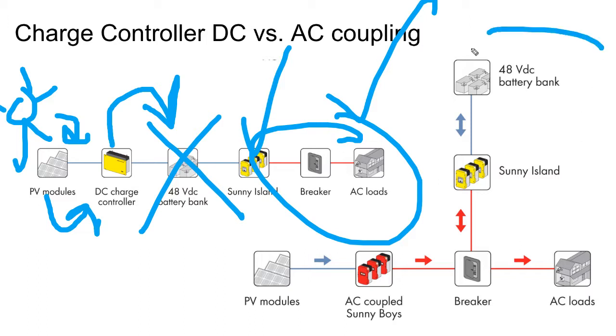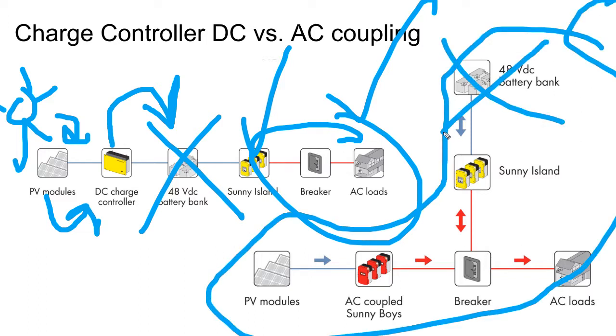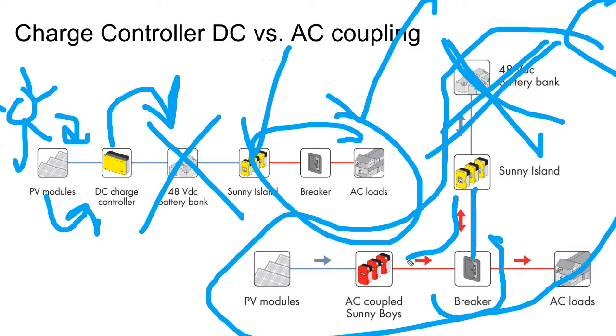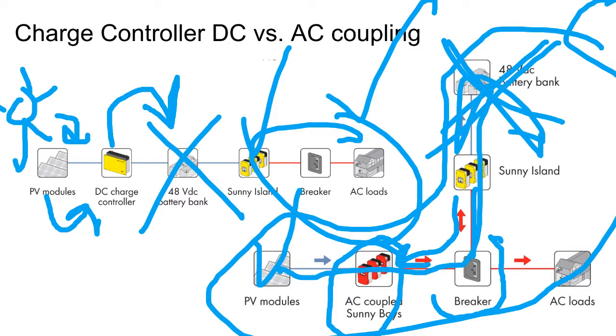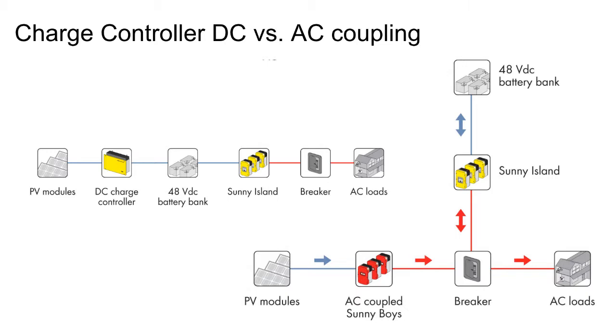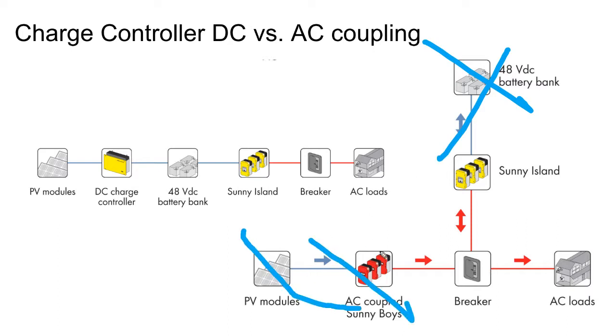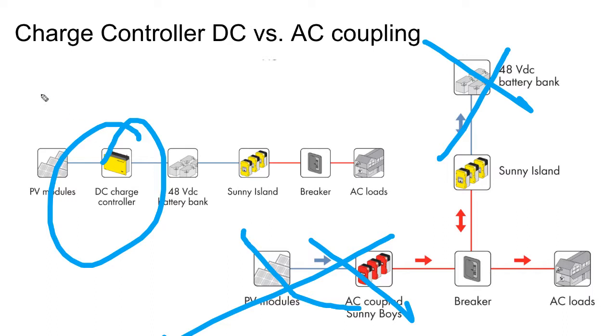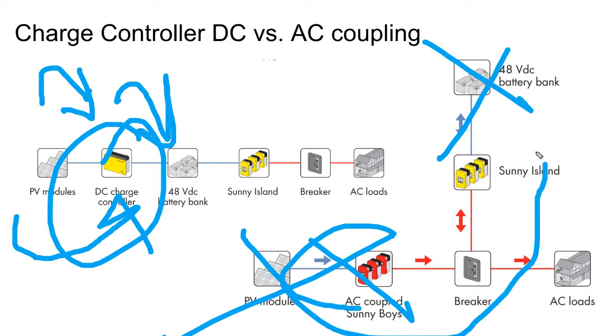Whereas in an AC coupled system, if your batteries run out of juice, even if you do a configuration where you're powering your main breaker, all of a sudden you don't have the power necessary to turn the solar inverter back on so that the modules can start recharging the batteries. And so in an AC coupled system, the danger is your battery power could run out, and then it would be difficult to get your solar array to recharge those batteries. Whereas with a DC coupled system, it happens easily because the solar array is on the battery side. It doesn't have to go through multiple inverter systems to get to the batteries.